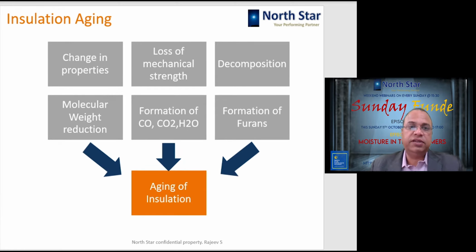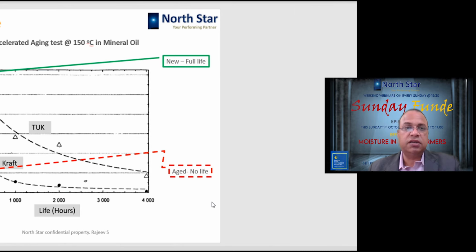Another way to look at the aging: what happens when aging is happening means the properties are changing, mechanical strength is coming down, material is getting decomposed, molecular weight is getting reduced, these gases are formed, and also furan is getting created in the oil. So all these factors happen when the aging is happening in the insulation.